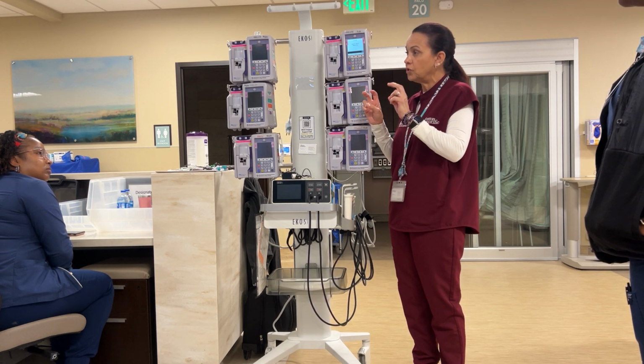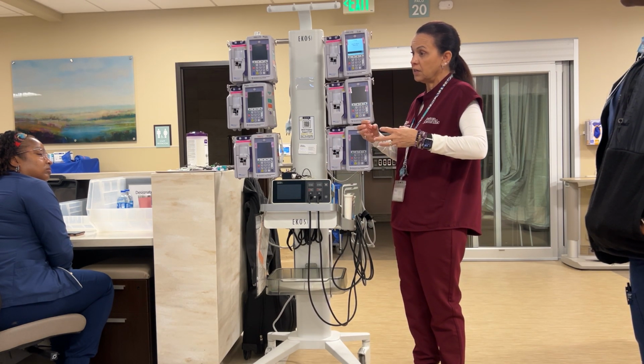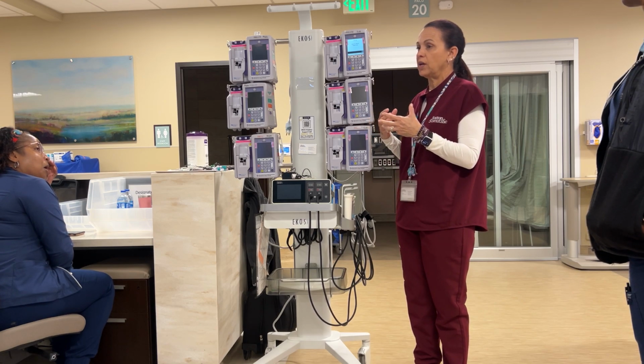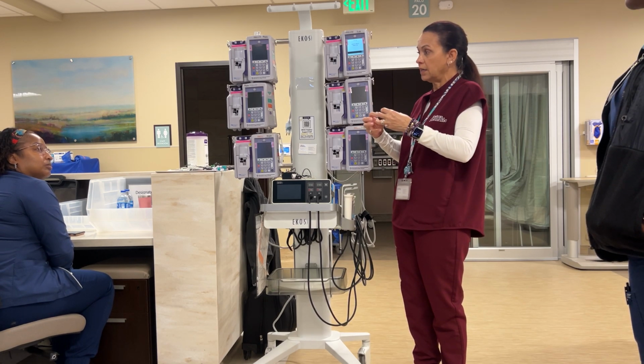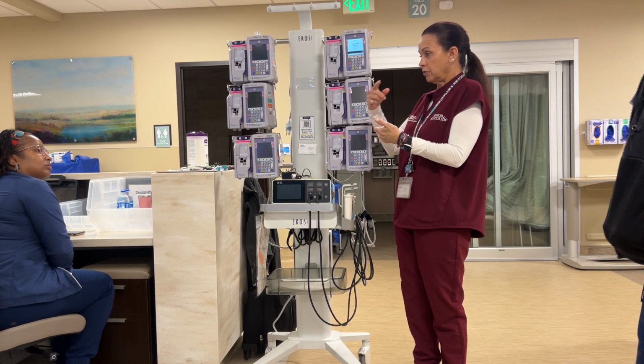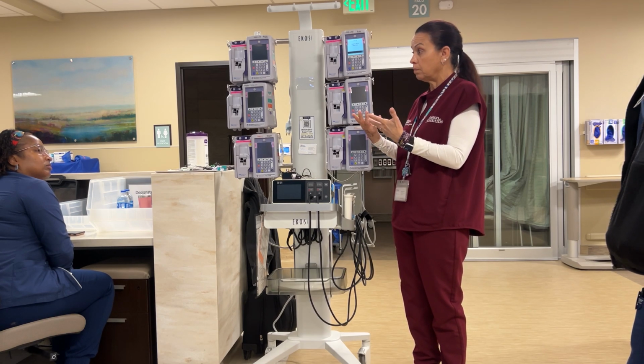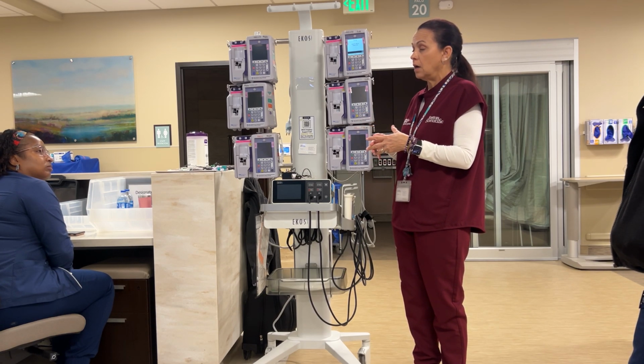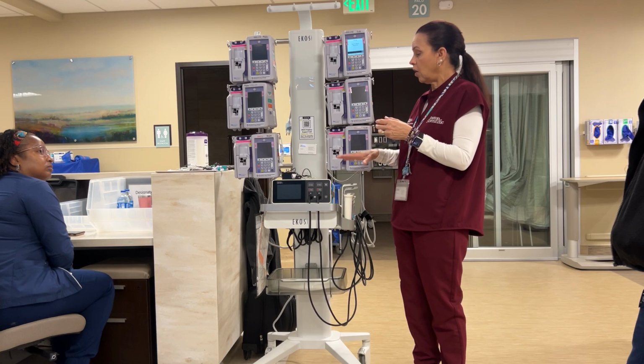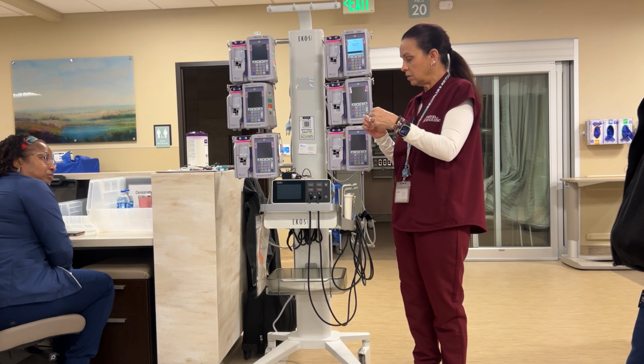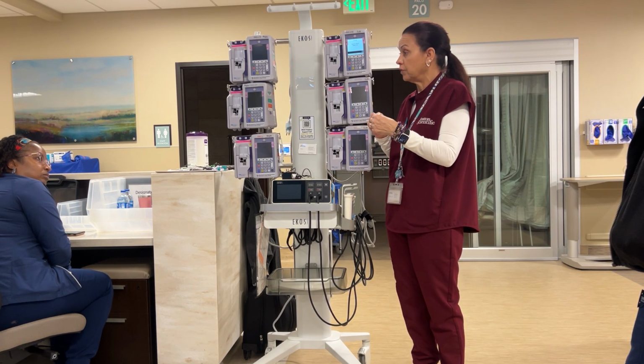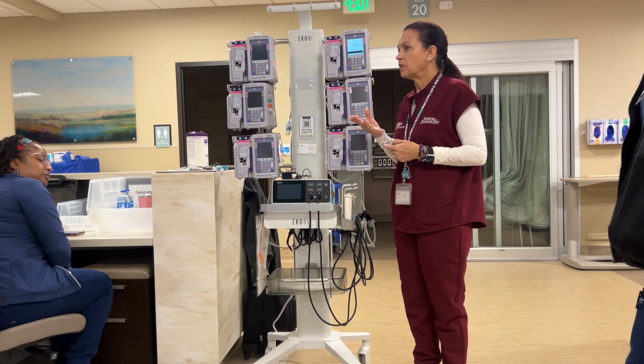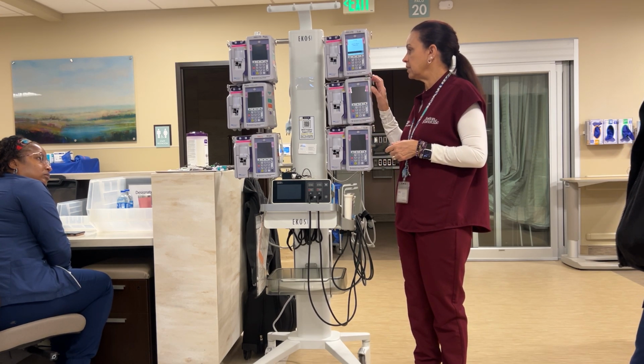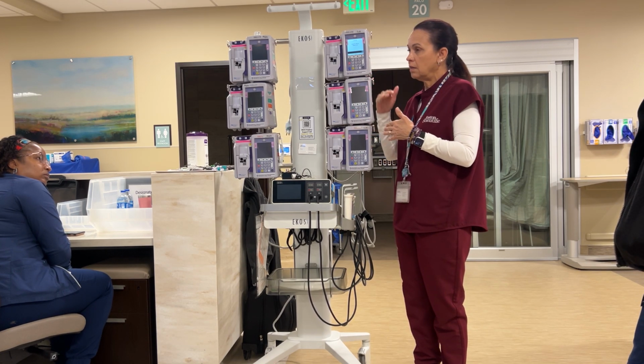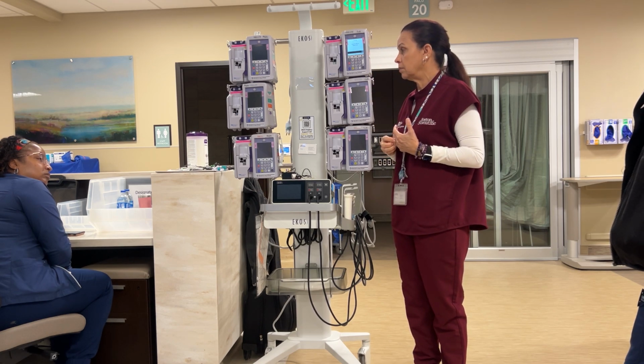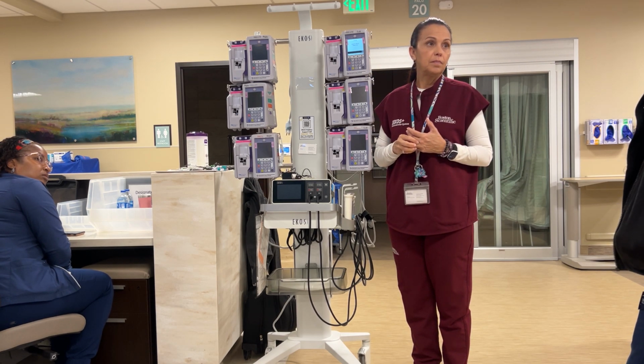If it's a true temperature error as far as the catheter is concerned, it would be a situation where you're in like a heavily clotted vessel where there's little to no circulation, blood flow around it, and it can cause the ultrasound core to overheat. So that's where the coolant would be titrated up by 10 ml increments. And the coolant is always sodium?